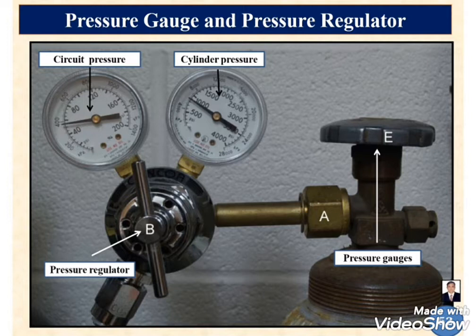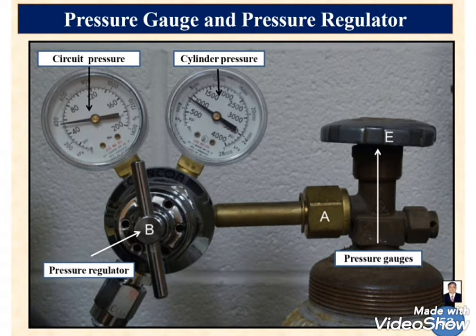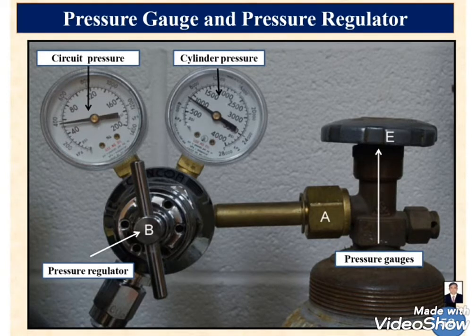So with the help of this second dial, we fix it. It indicates on the gauge, fixed at 40 to 50 psi. In Indian measuring units, it is generally fixed between 3.5 and 4 kg per cm square. High pressure gas from the cylinder is dangerous to the patient; it ruptures the lung tissue. So regulate it properly with the help of the pressure regulator.